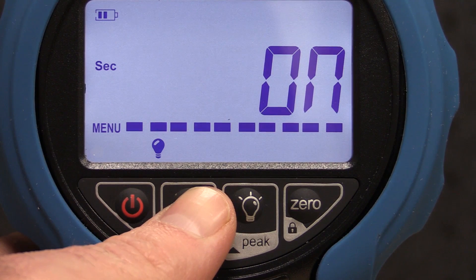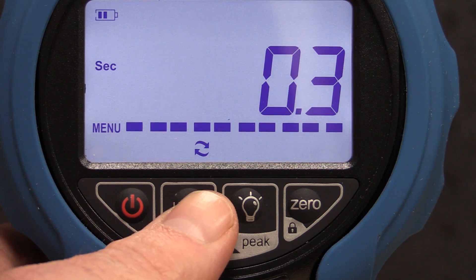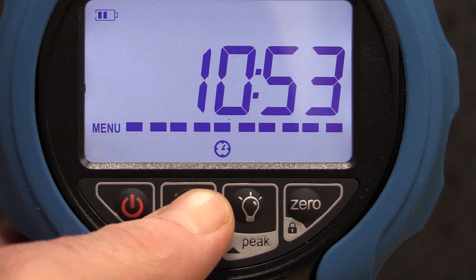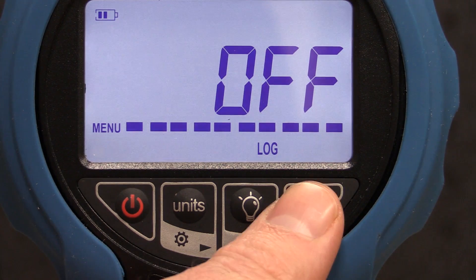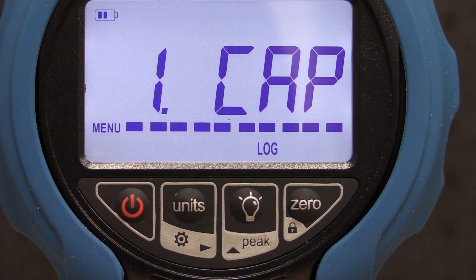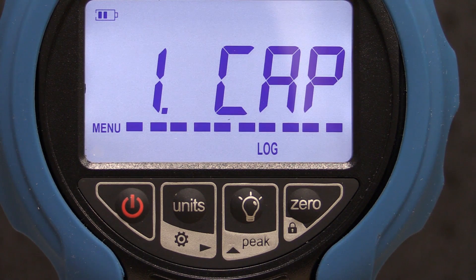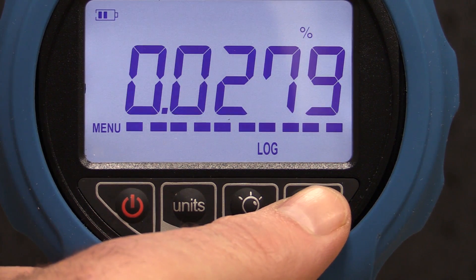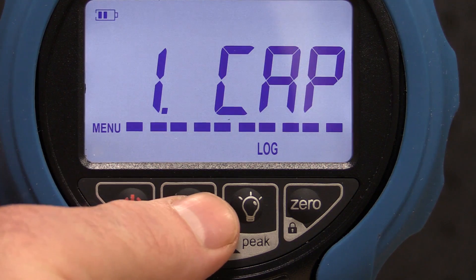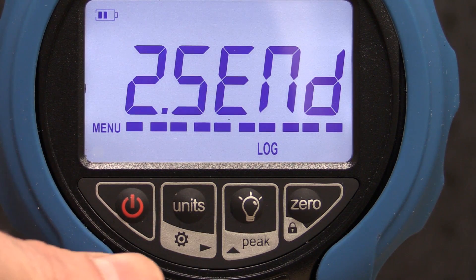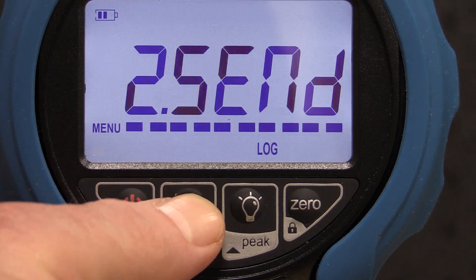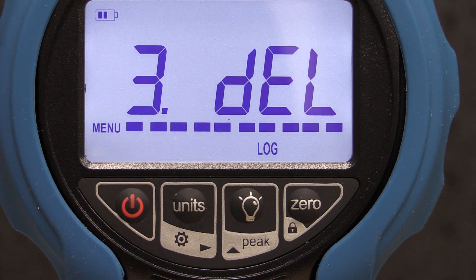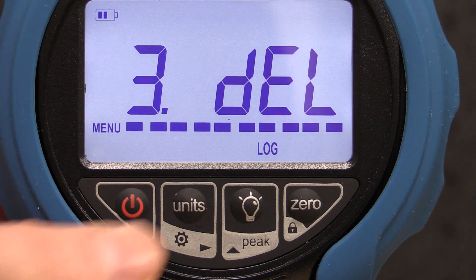From the main screen, press and hold the Units key to access the main menu. Press the Units key again to navigate to the right until you see Log and press zero to enter into the Log menu. CAP stands for Capacity, which shows the percentage of the total memory used. Press the Units key to advance to the second menu Send, which is intended to upload data manually. The third menu allows for the deletion of all log data. This menu is password protected.